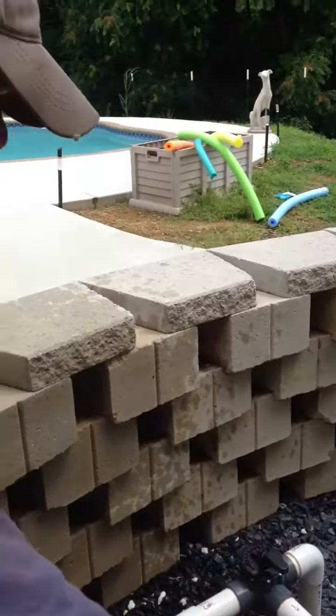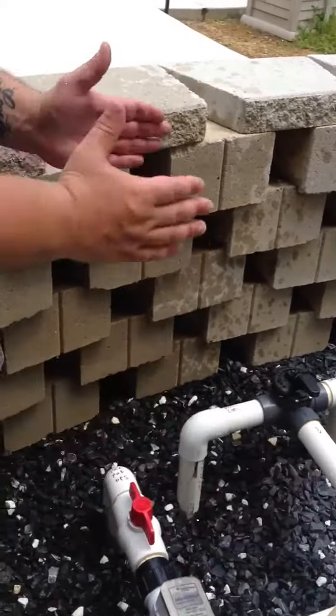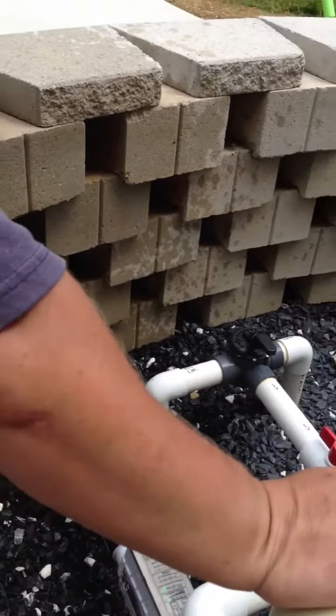When the system's running, never close this valve. That'll create back pressure — you don't want the back pressure. That would be bad. I've been to two jobs this week where someone had done that.